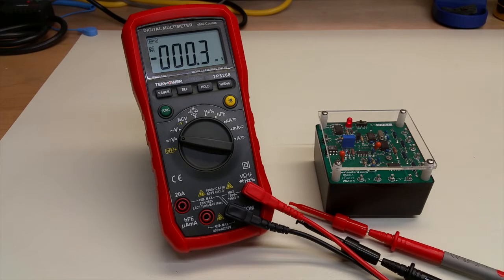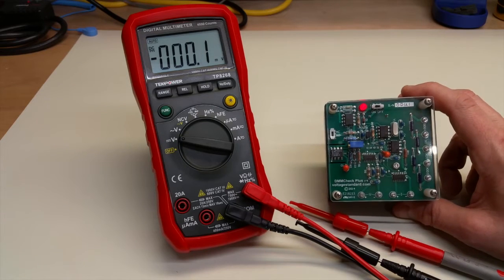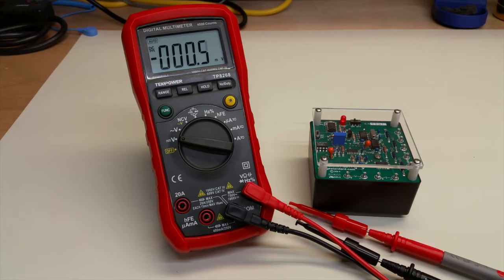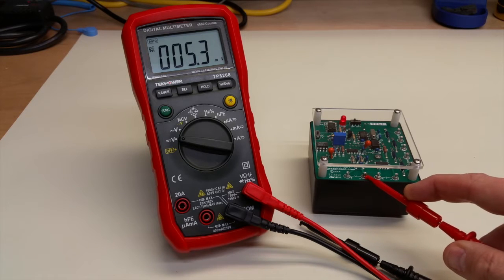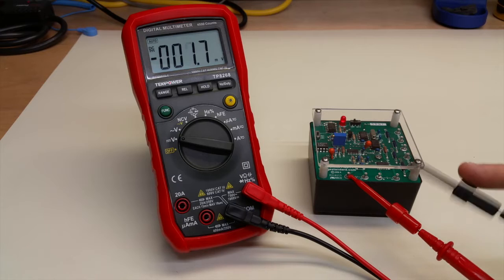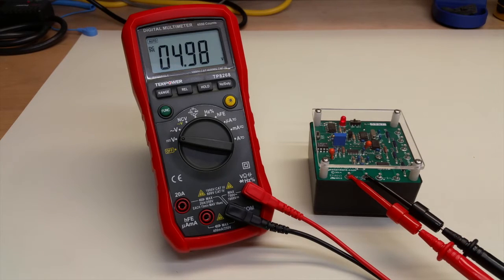So we can check, using a very nice voltage and current standard that also has some high precision resistors built into it as well, we can check at least the DC voltage performance or accuracy. I'm just going to clip on the leads to the DC voltage, and this should read 5.00, and there's another zero past that in terms of the actual true voltage. And what you see here is we're reading 4.98 volts instead of 5.00. That's actually fine. That is within specifications.